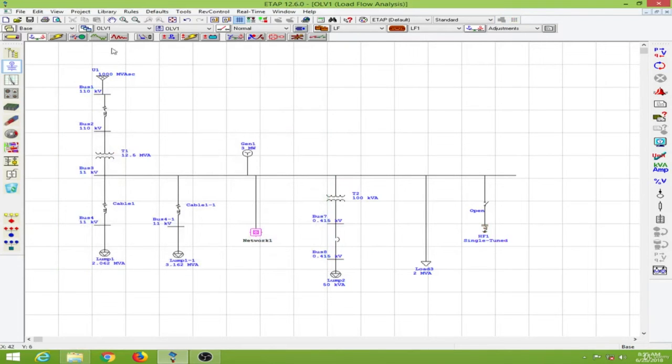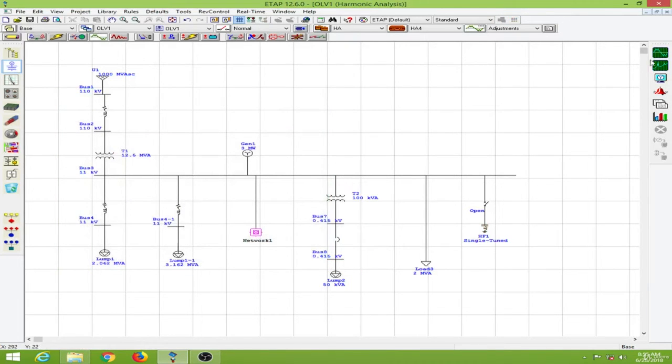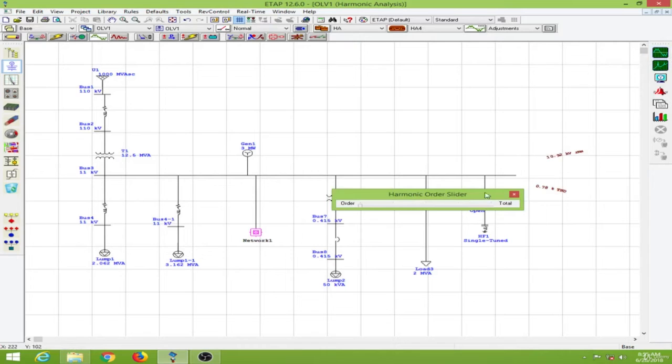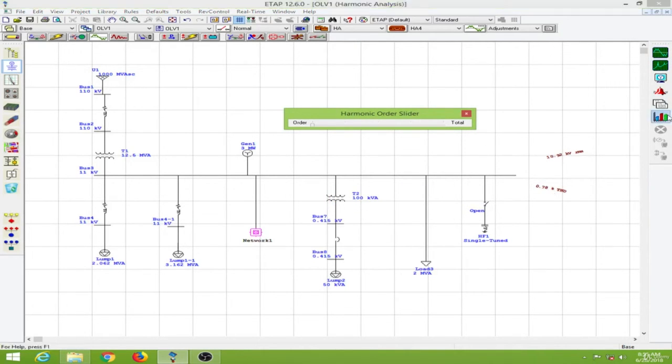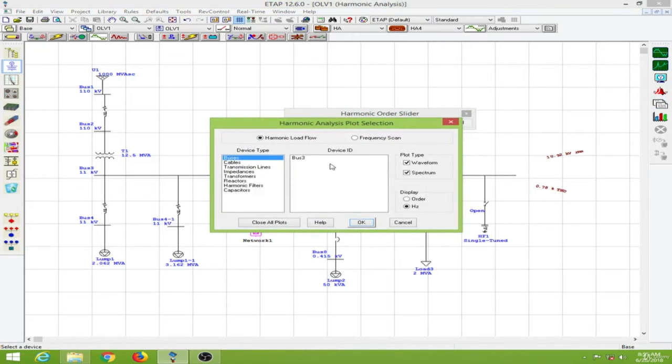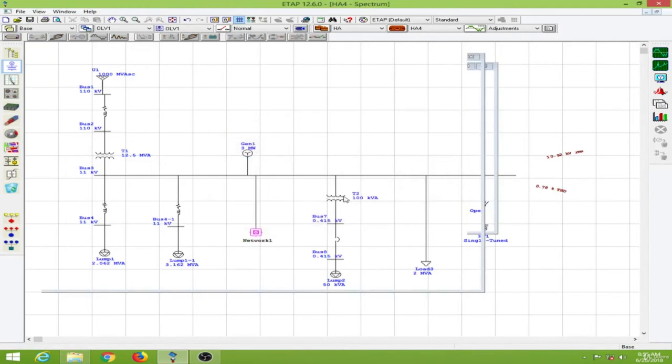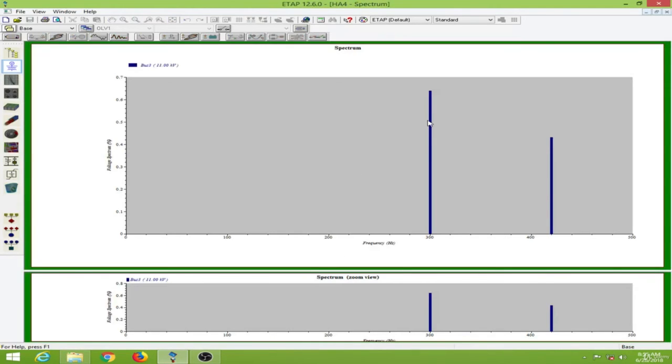Again we will run the harmonic analysis without the filter. The total harmonic distortion is about 0.78%. We'll go to the plots to observe the spectrum.